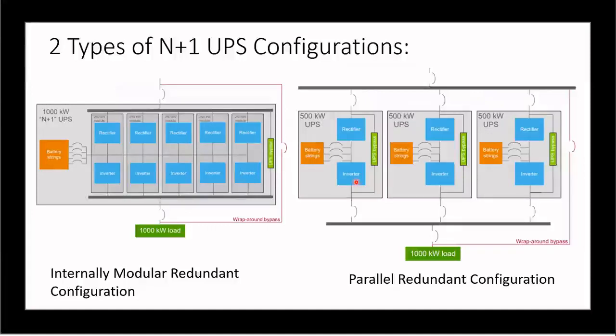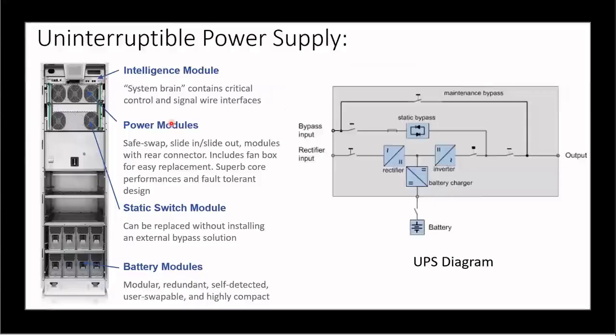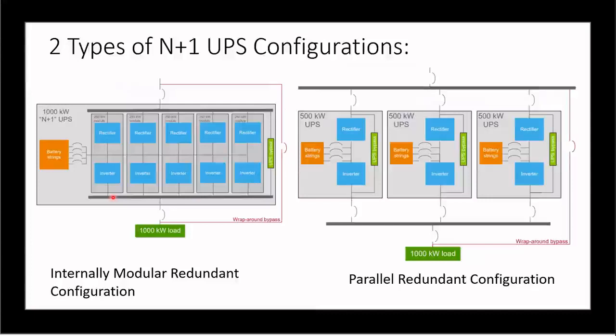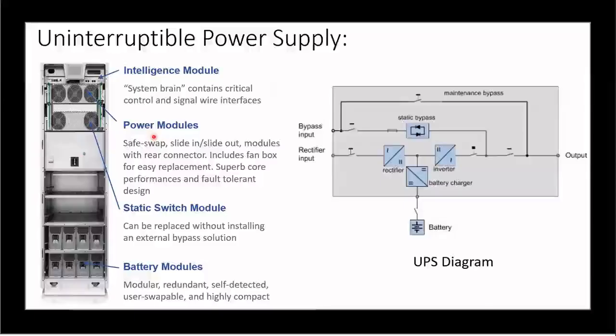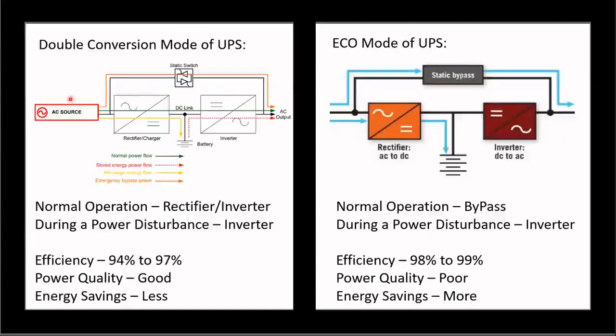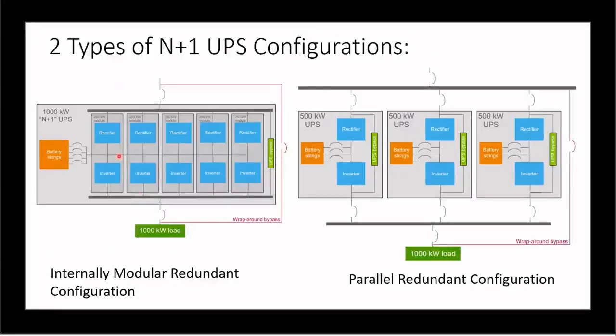Then these are the two types of N+1 UPS configurations. So this goes back to the UPS diagram here. This is the modular UPS, right? Now, the internal modular redundant is when a single UPS will have more modules. So this is just one kind of UPS, but there are different types. There will be a UPS that has more power modules. So this power module supports 250 kilowatt. Here, our load is 1000 kilowatt, so if we have 250 kilowatt power modules, we need 4 power modules, right? Now, what is this fifth doing here? If something goes wrong with one unit, then this will help to supply the load. That is called the internal modular redundant configuration.